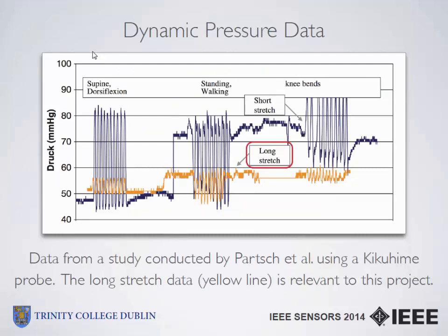This is a sample of existing dynamic pressure data taken using the Kikuhime probe. The yellow line corresponds to the type of bandage being investigated, which is a long-stretch bandage. The existing data clearly shows what the patient is actually doing at the time. For example, flexion of the foot produces a regular sine wave action. Then standing shows a flat section, walking produces more motion with a regular sine wave, and knee bending is also quite apparent. This is the type of dynamic pressure data we were aiming for.